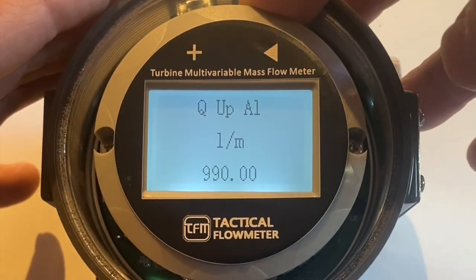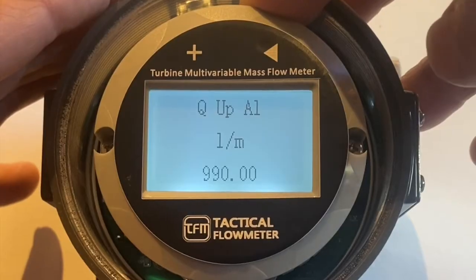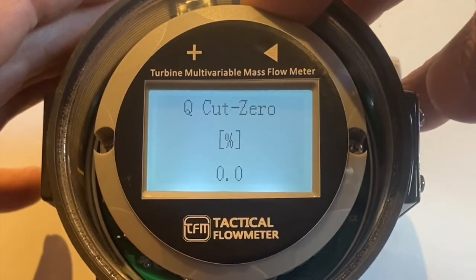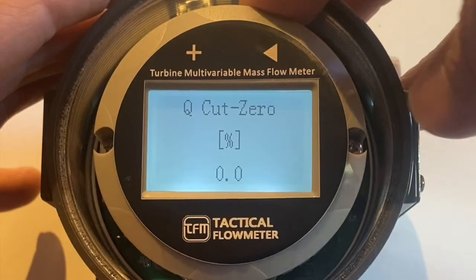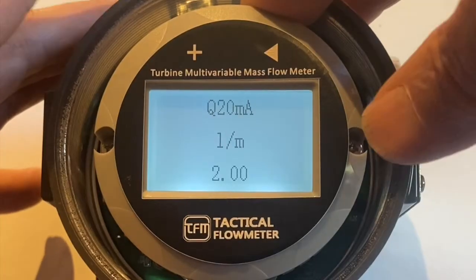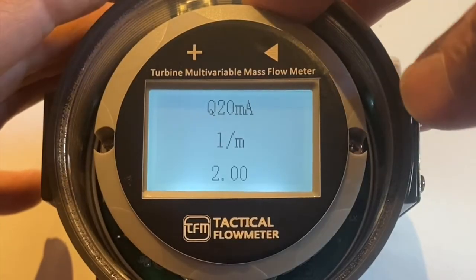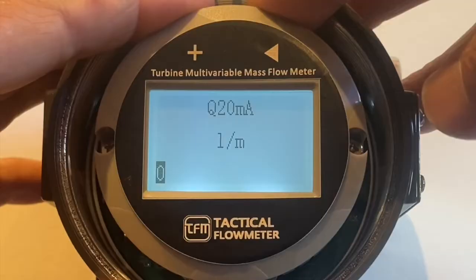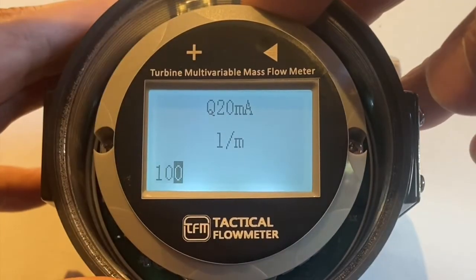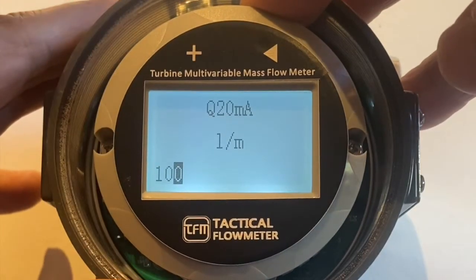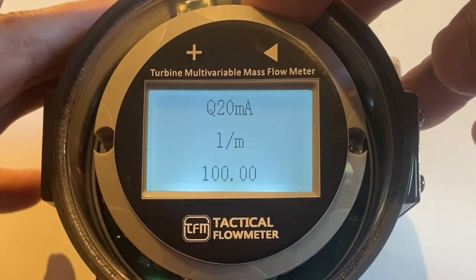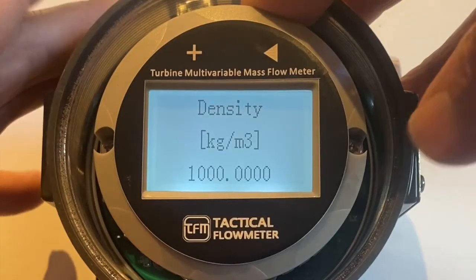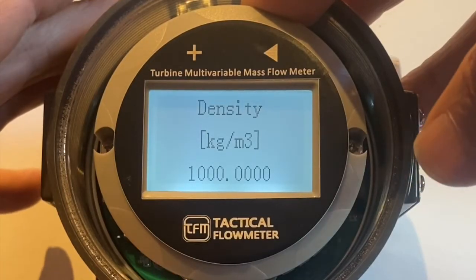Let's set this flow rate to 1000. Cut off for the low flow — you could set that to the percentage. The 4 to 20 milliamps, I'm going to set it to 100 liters per minute. One, zero, zero. Long hold on the right, 100 liters per minute.